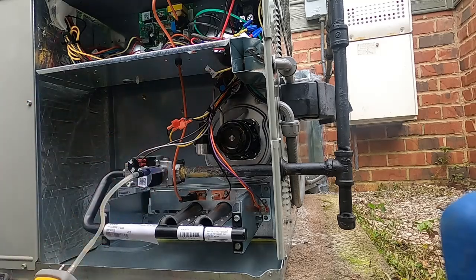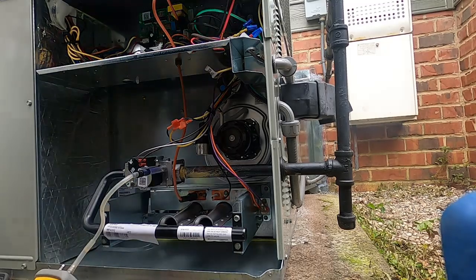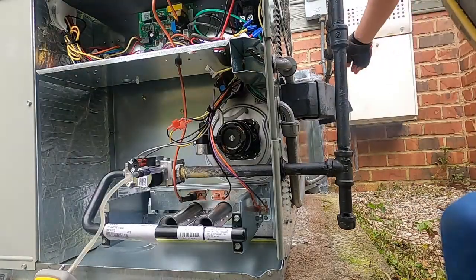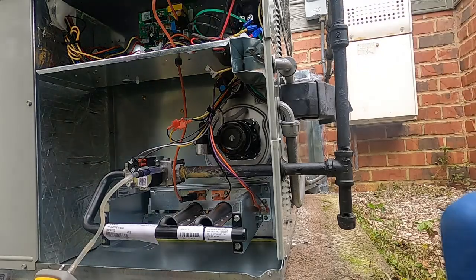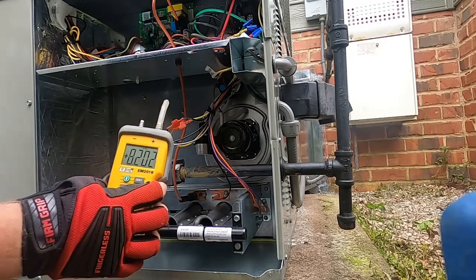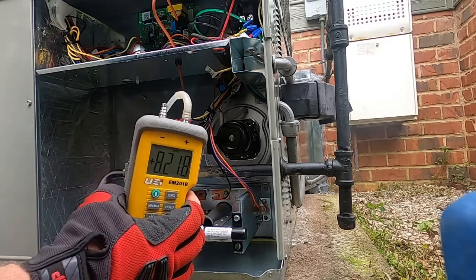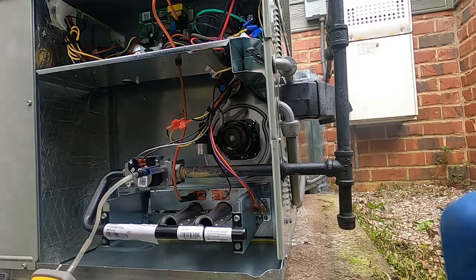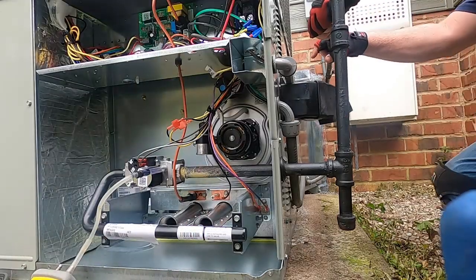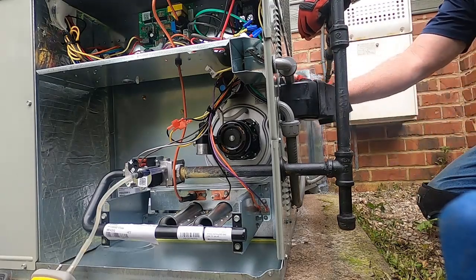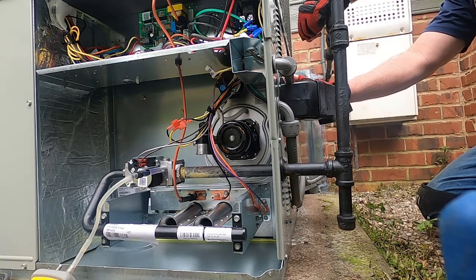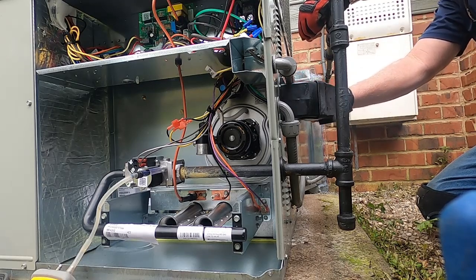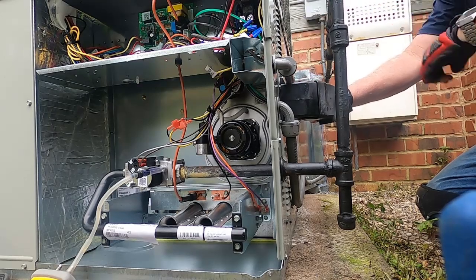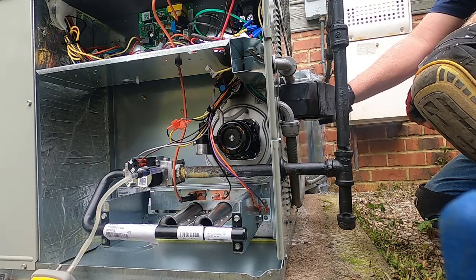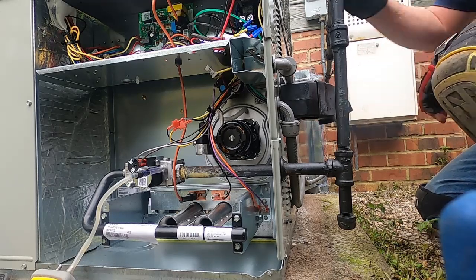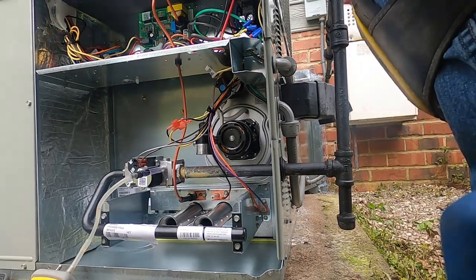So I'm connected here. I'm going to turn my gas shutoff back on, see what our inlet is. Inlet is 8.2 right there. Let's see what the data plate is telling us we need. Water column, inlet pressure, minimum. So our max gas supply pressure is 13 inches of water column, and our minimum is 5. So at 8, we're just fine. That is going to be good.